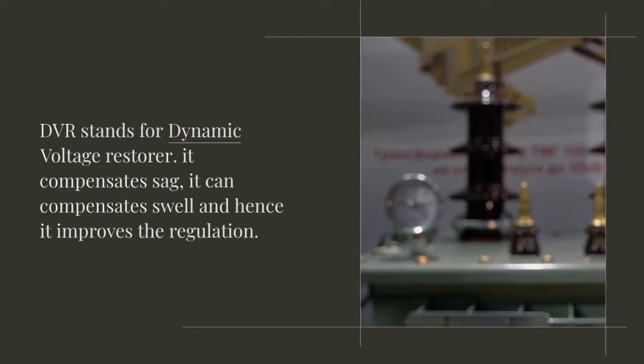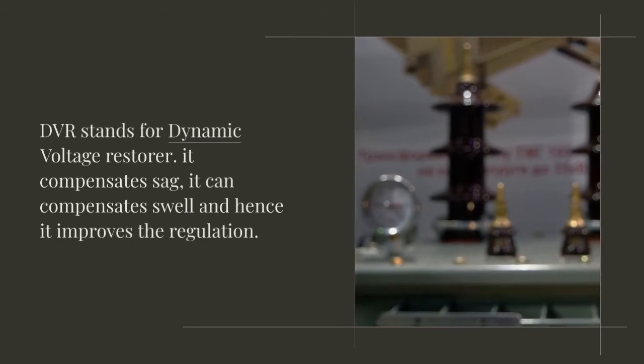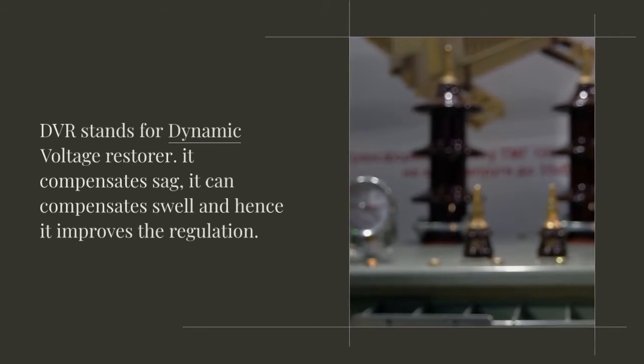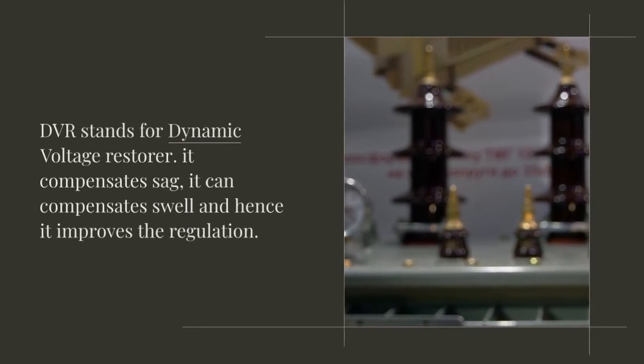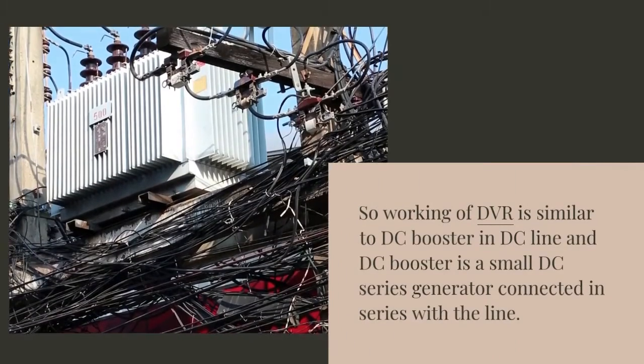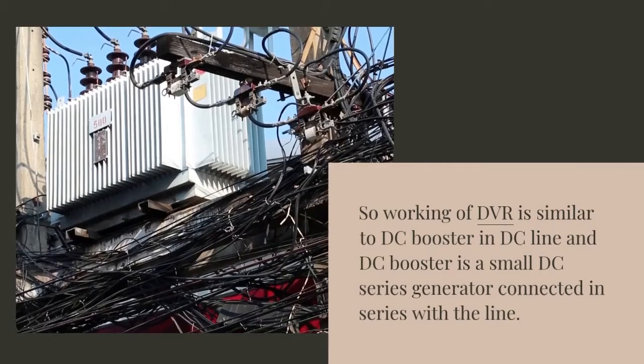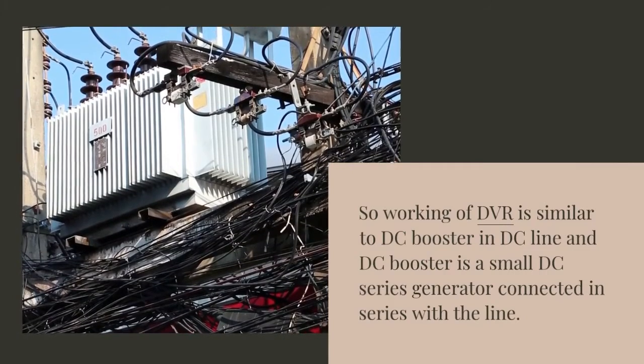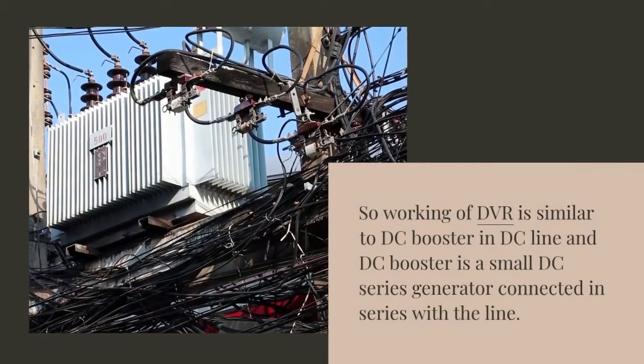DVR stands for Dynamic Voltage Restorer. The functions: it compensates sag, it can compensate swell and hence it improves the regulation. So working of DVR is similar to DC booster in DC line and DC booster is a small DC series generator connected in series with the line.